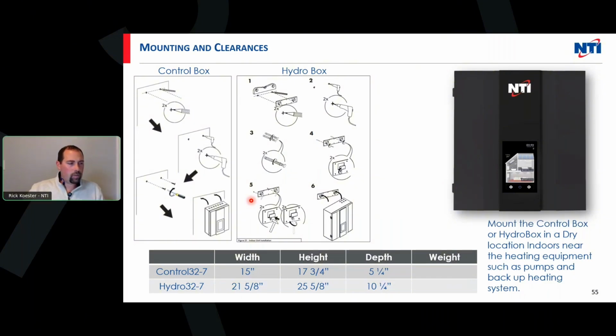Mounting the indoor units, fairly simple. The control box can be mounted directly to the wall, has some mounting holes in the back there. So we have the hardware that comes with it, so they can mount that. I forgot to throw the weights in here again, so I got to add that. But the hydro box, being the heaviest, is about 66 pounds with all the components in there. That will have a bracket just like how boilers do. They mount it, level it, all of that, and then just hang the hydro box on it. So that's fairly simple. Control box weighs probably less than half the weight of the hydro box, so 66. I want to say it's like 28 pounds to 24 pounds for the control box. Still want to make sure it's being secured properly, for sure.